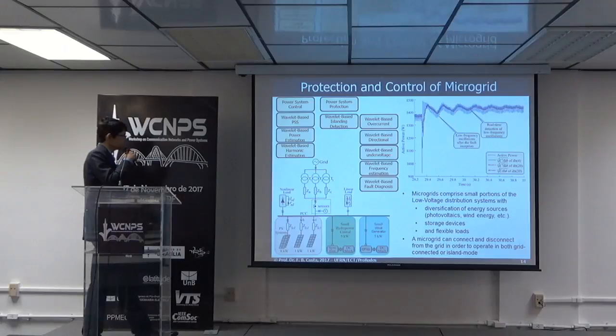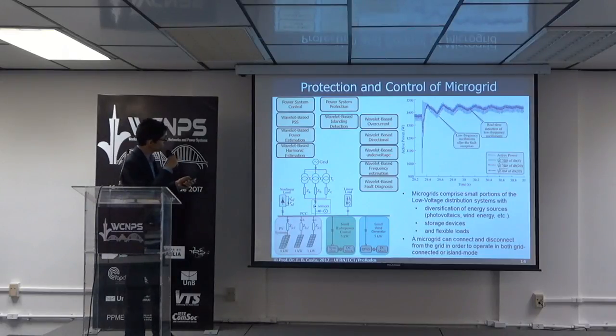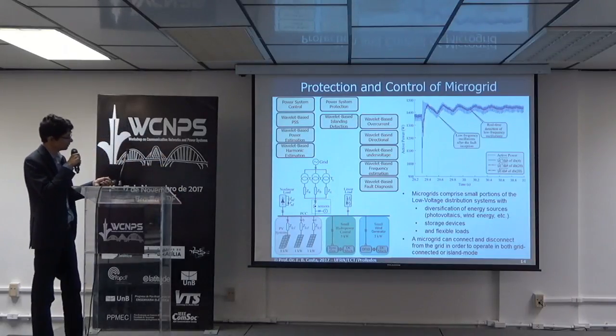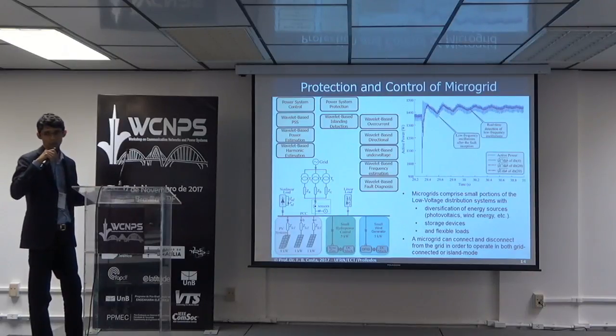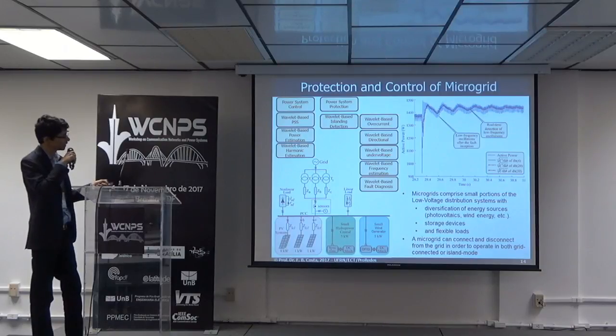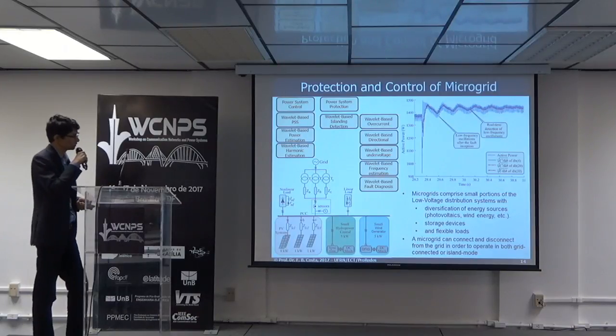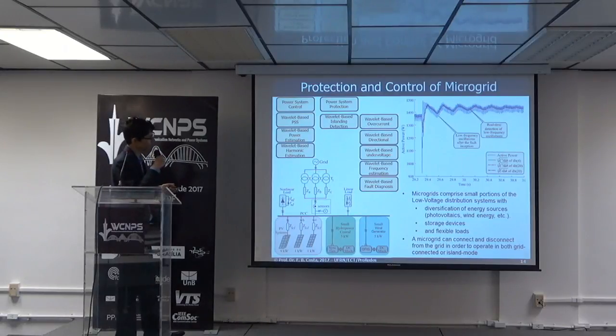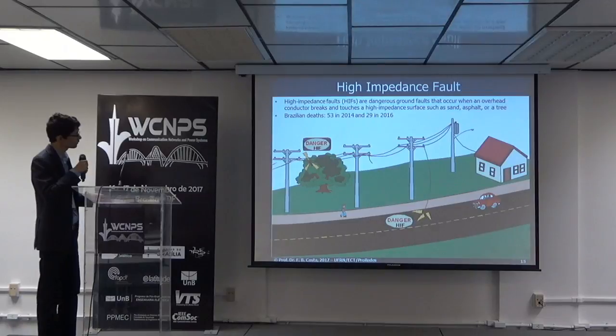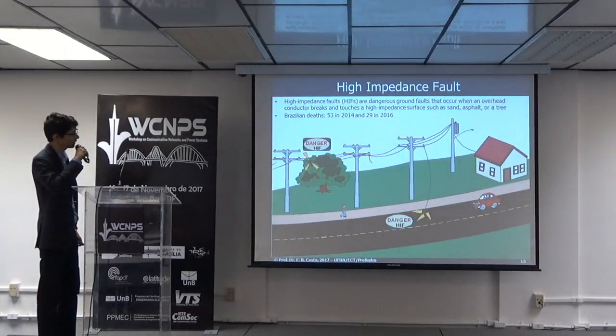So in this case, the wavelet transform could be used in a PSS, power system stabilization, in the control system. The wavelet transform information, such as power estimation and harmonic estimation, is very important for control as well as for protection. Regarding the island protection, the wavelet-based overcurrent, directional, under voltage, and so on, could be used in these scenarios. We have here another example.